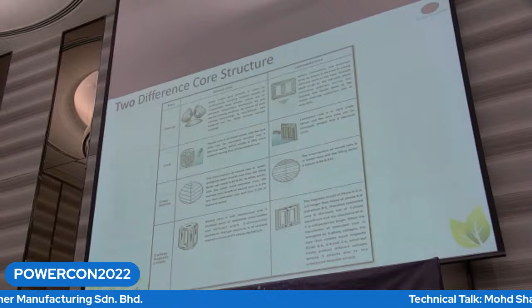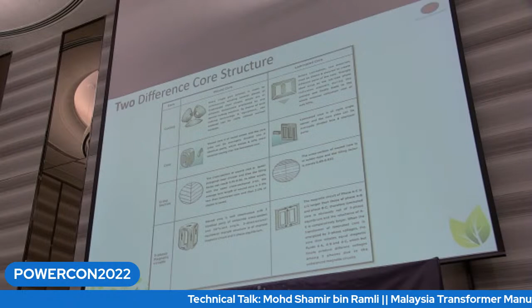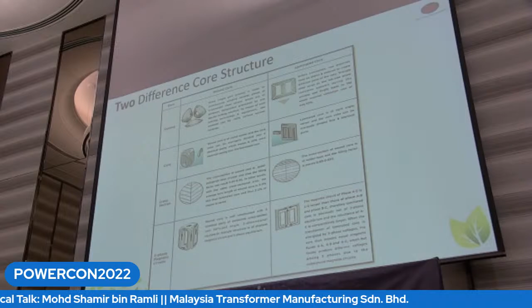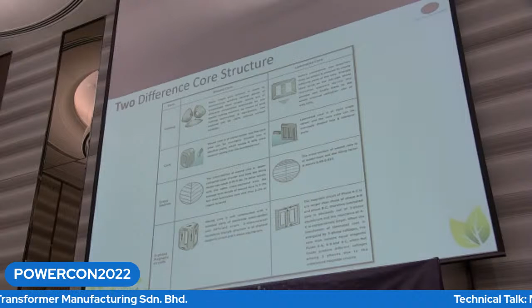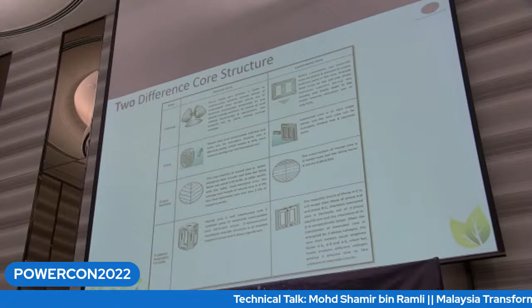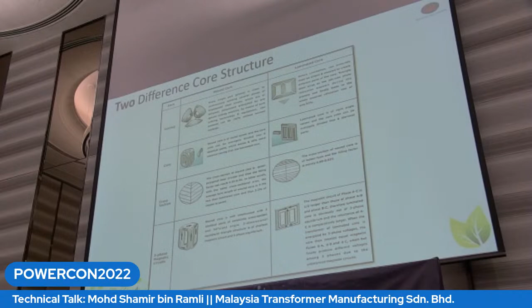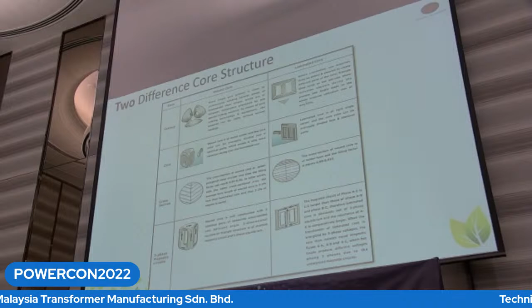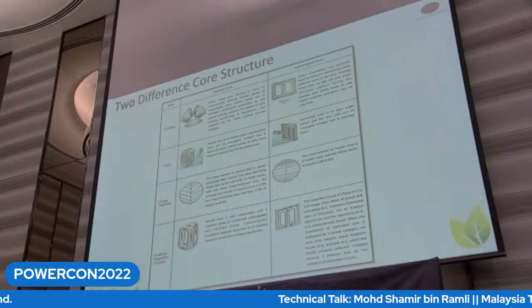These are two different core structures. You can see the difference in cutting between the wound core versus the laminated core. The wound core has a unique cutting method, which results in reduced waste for the core. The rounded corners of the core also give more material savings, so when you put the copper foil on top, you get reduced copper usage as well. In terms of cross section and the 3-phase magnetic circuit, the 3D wound core gives a more balanced magnetic circuit.